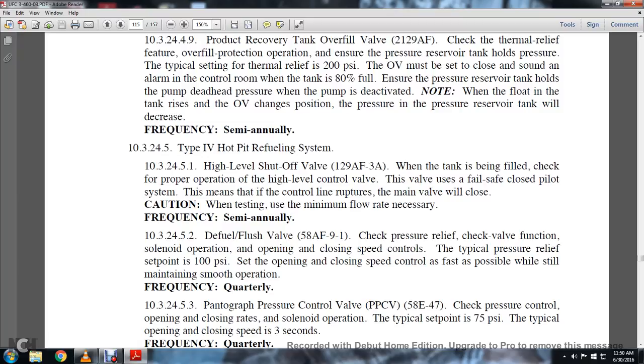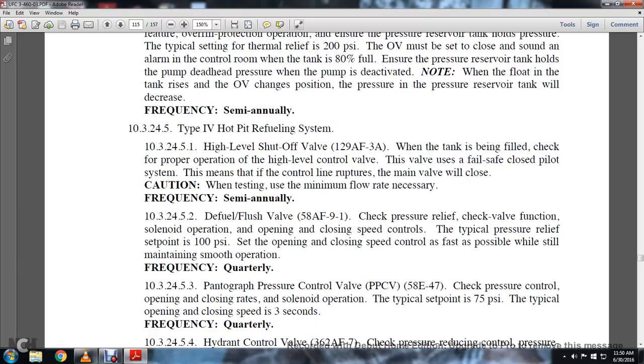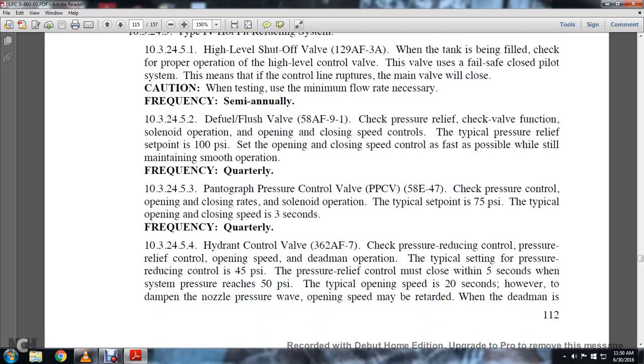Typical pressure relief is set at 100 psi. Set the opening and closing speed control as fast as possible while still maintaining smooth operation. This inspection is done quarterly. Pantograph pressure control valve, or PPCV: check the pressure control opening and closing rate and solenoid operation. The typical set point is 75 psi. The typical opening and closing speed is 3 seconds. That should be done quarterly.